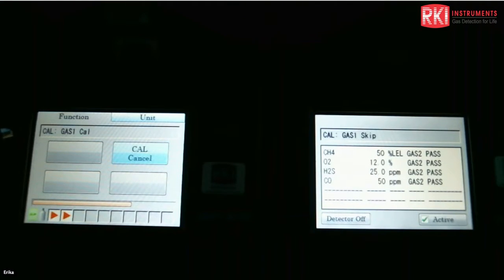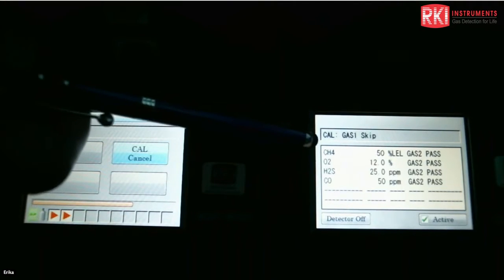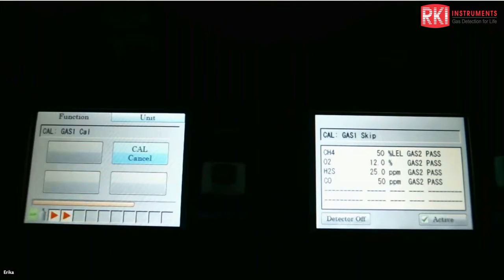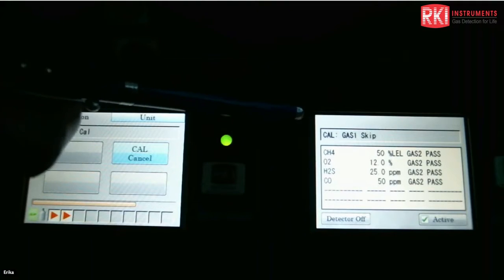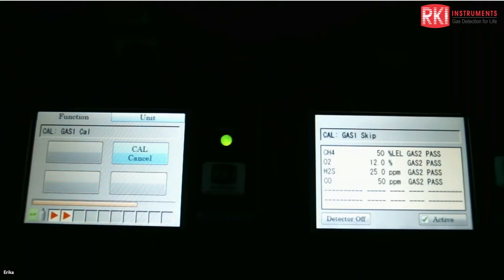Yeah, so you see this one says gas 1 cal, this one gas 1 skip. Gas 1 is the PID, so this one doesn't have the PID, so it's just skipping it and putting the gas to whatever the GX6000 needs. If you can see, there's also a status icon over there. It just means it's doing the calibration on both of them at the same time.